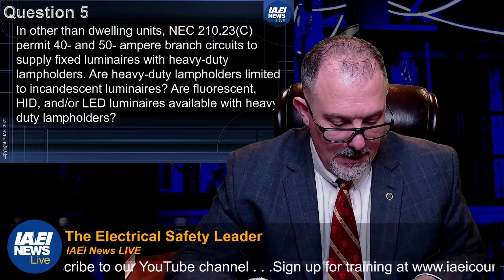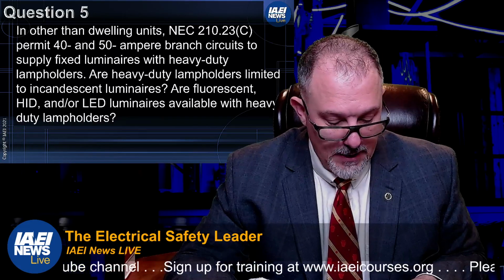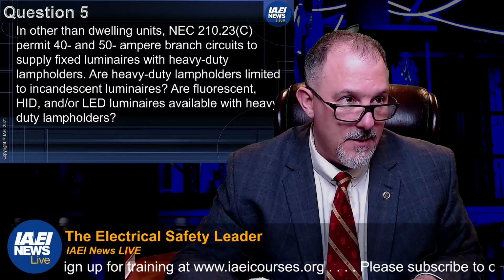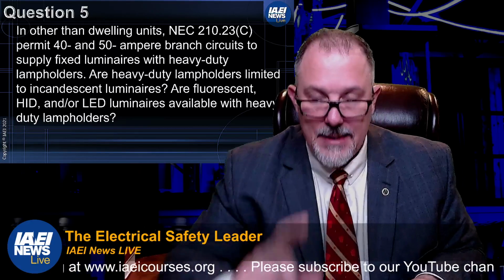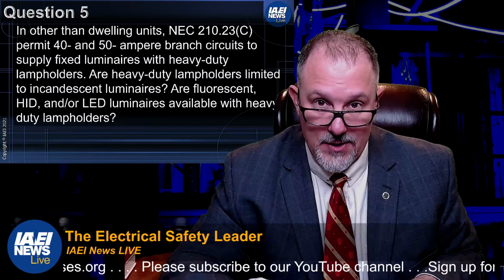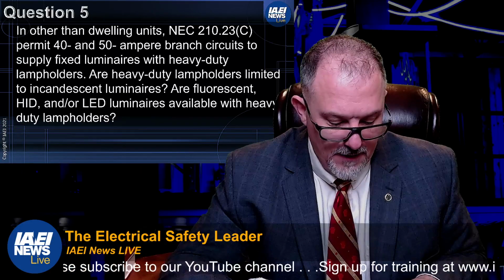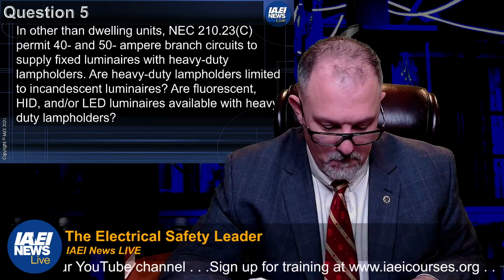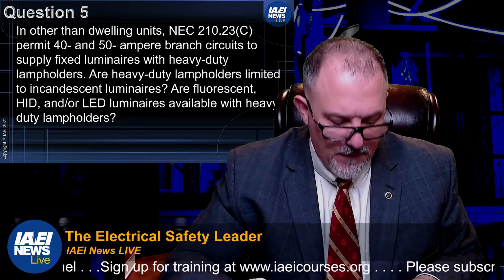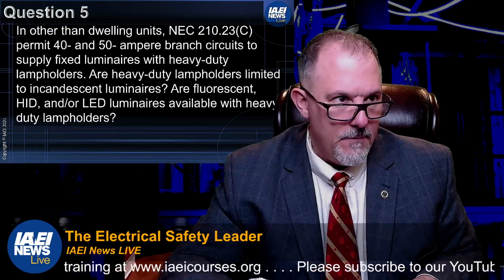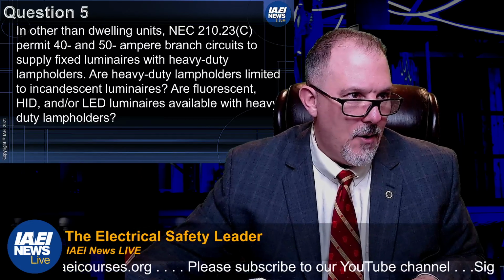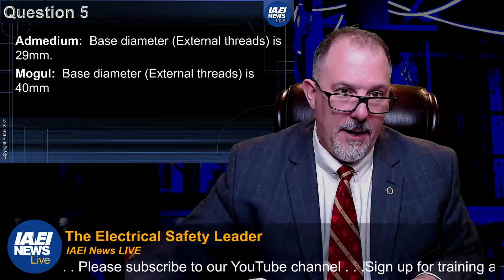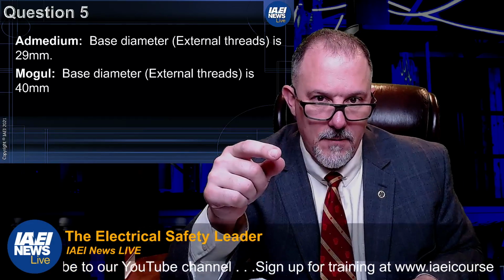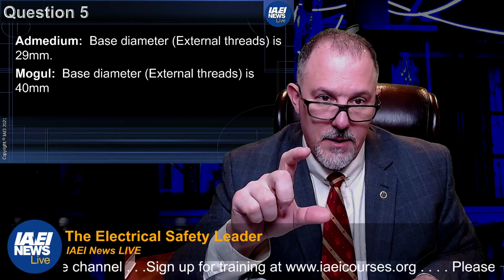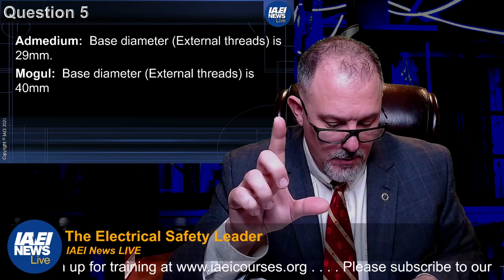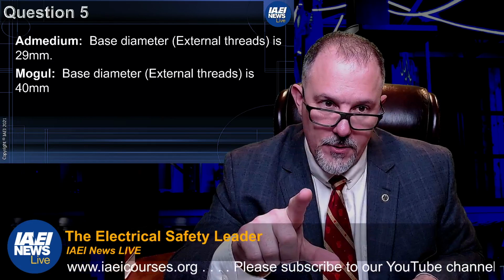Now, what does that mean? 210.21(A) gives us some guidance. That unit has to have a rating not less than 600 watts if of the admedium type, or not less than 750 watts if of any other type. Well, oh my goodness. What is that, right? Admedium. The base diameter, the external thread, is 29 millimeters. Our mogul base is 40 millimeters. Both of those are heavy-duty lamp holders.